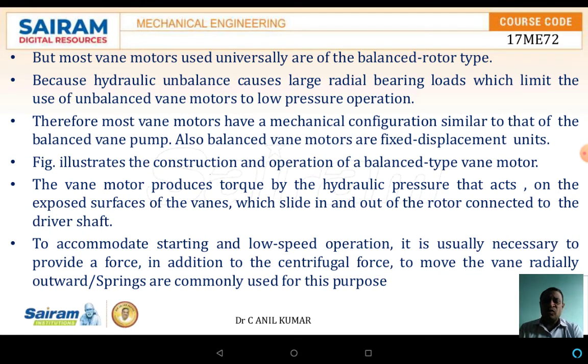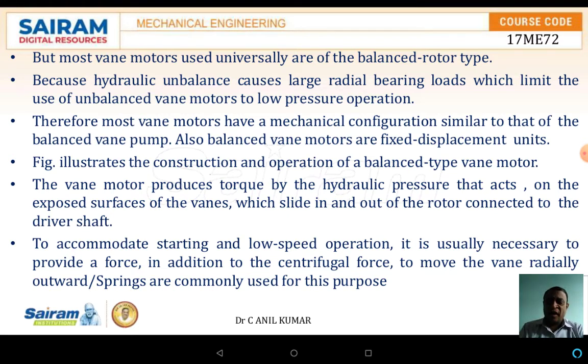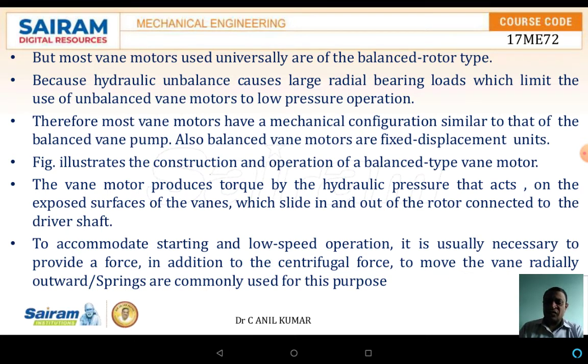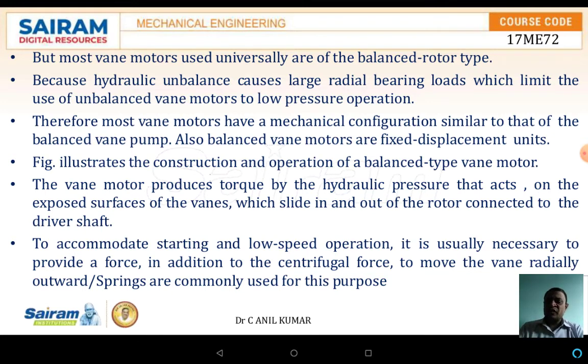The vane motors are fixed displacement units. The figure illustrates the construction and operation of the balanced type of the vane motor. The vane motor produces torque by the hydraulic pressure that acts on the exposed surface of the vane which slides in and out of the rotor connected to the driver shaft. To accommodate starting and low speed operation, it is usually necessary to provide a force in addition to centrifugal force to move the vane radially outwards. Springs are commonly used for this purpose.